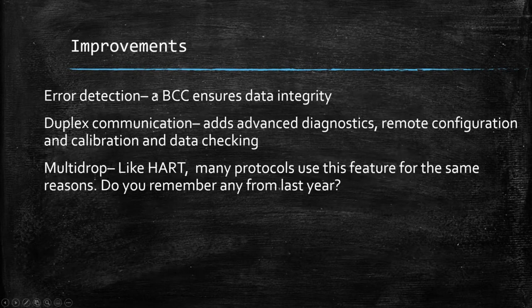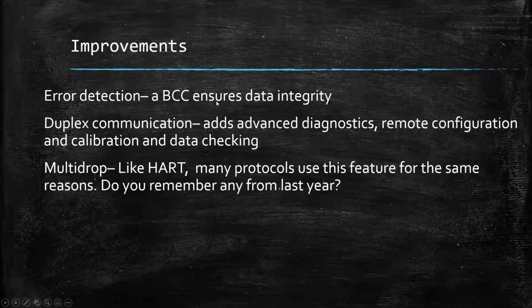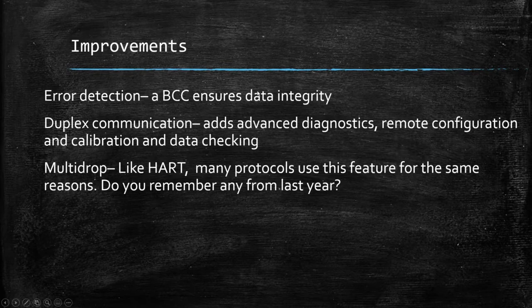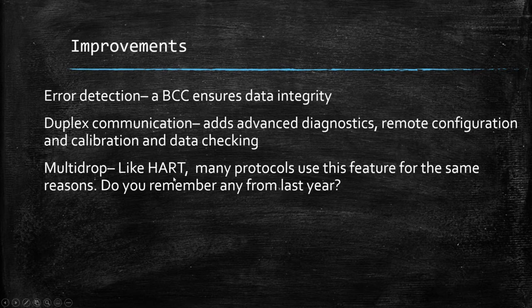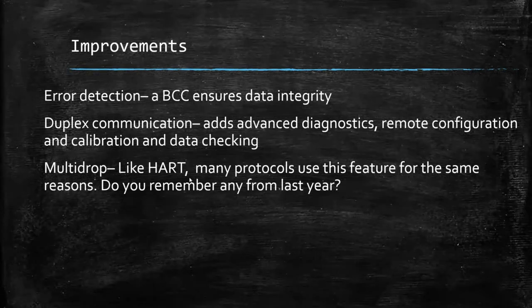Error detection — how do they do it? A block check character is a method of error detection used to ensure data integrity, so we know whether the data we're receiving is good. Before with analog, we didn't have a way to tell — we just took it at face value. Duplex communication, two-way communication, adds advanced diagnostics, remote configuration and calibration, as well as data checking capabilities. And a big thing about digital is multi-drop, like HART and many others we'll be discussing. In a bus, it's cheaper to wire with less wire — those are some of the benefits of multi-dropping.